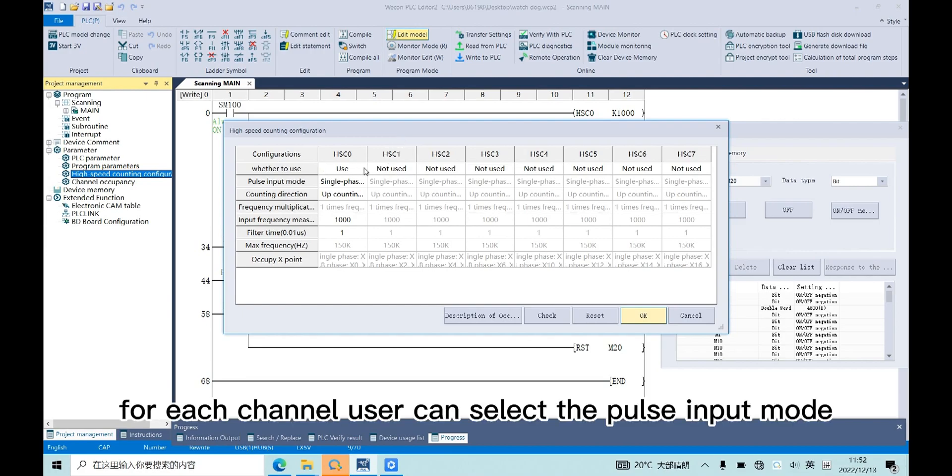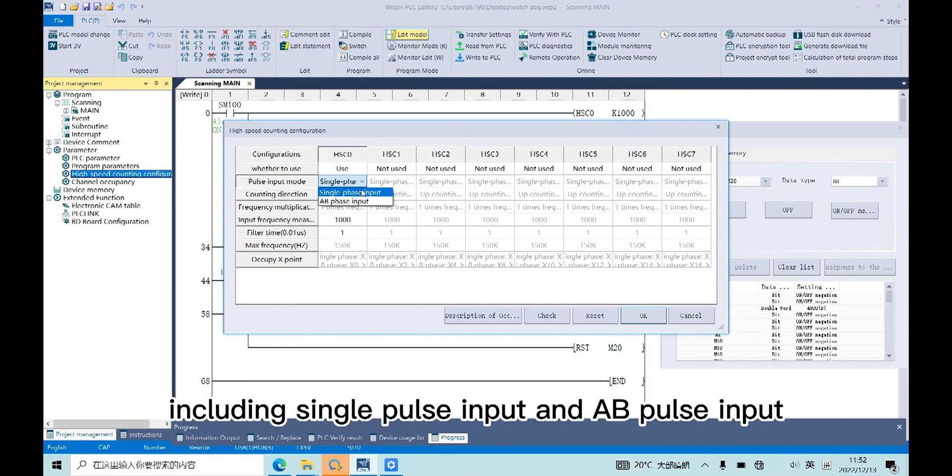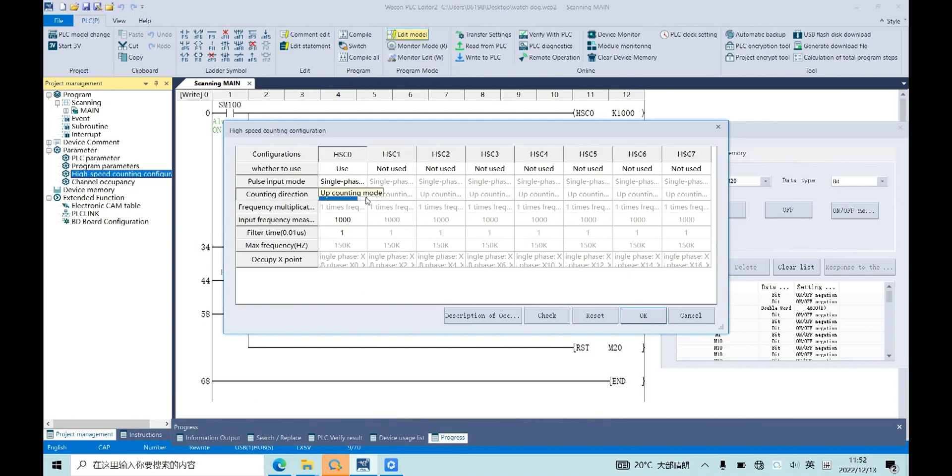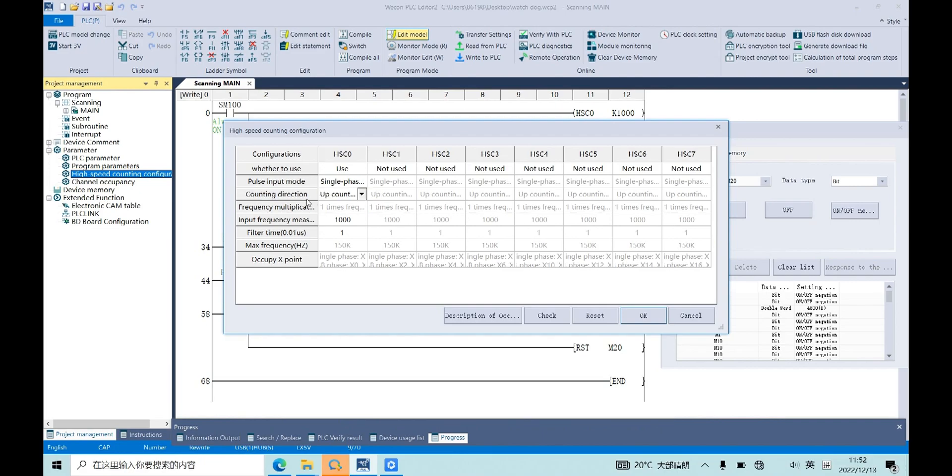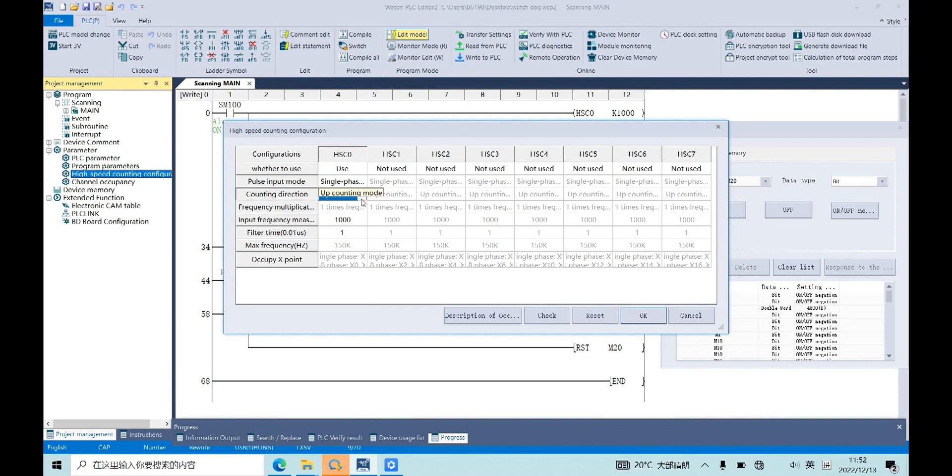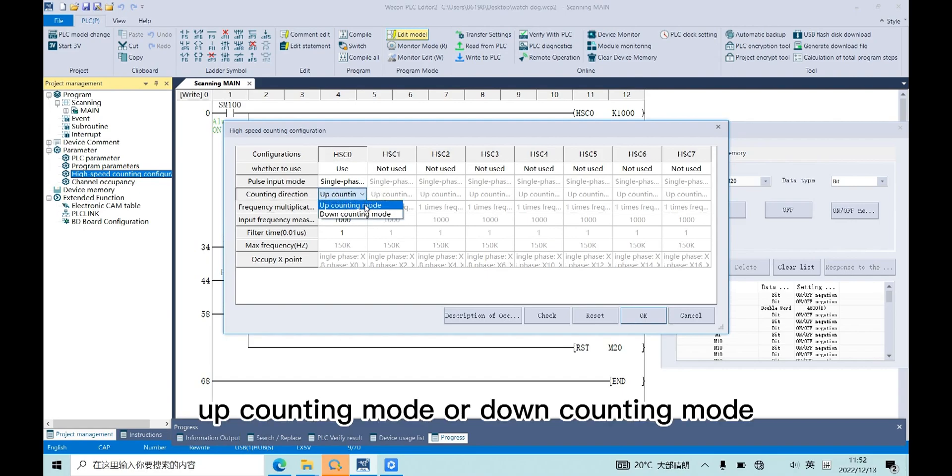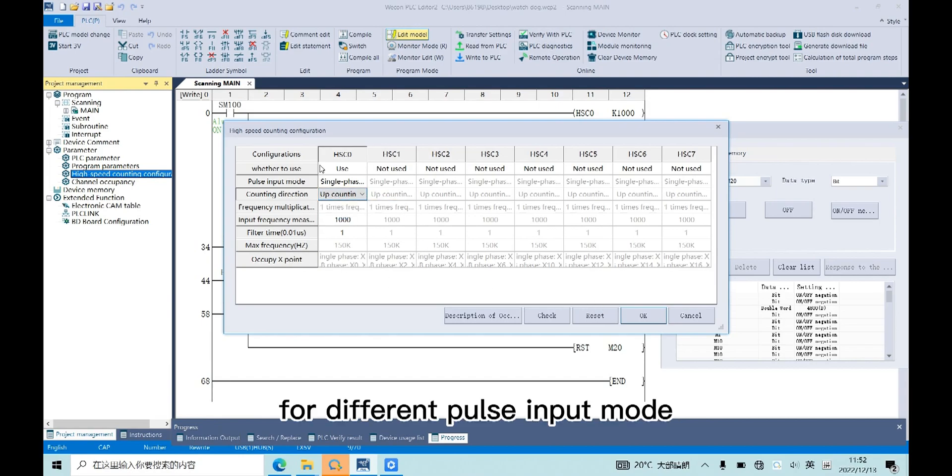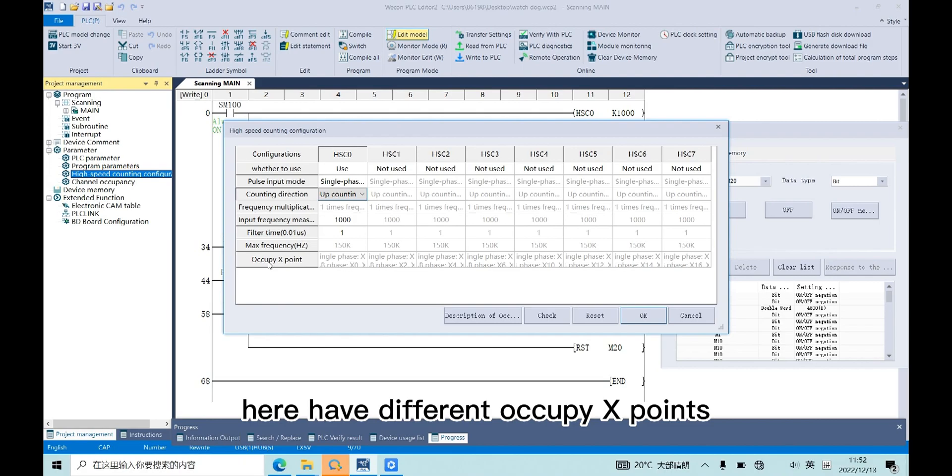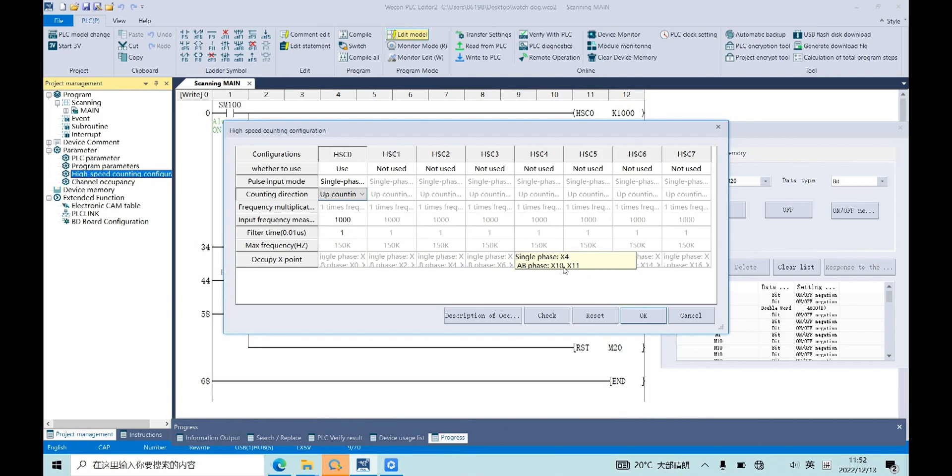For each channel, user can select the pulse input modes, including single pulse input and AB pulse input. And also, user can select the counting direction, up counting mode or down counting mode. For different pulse input modes, there are different occupy X points, user can check here.